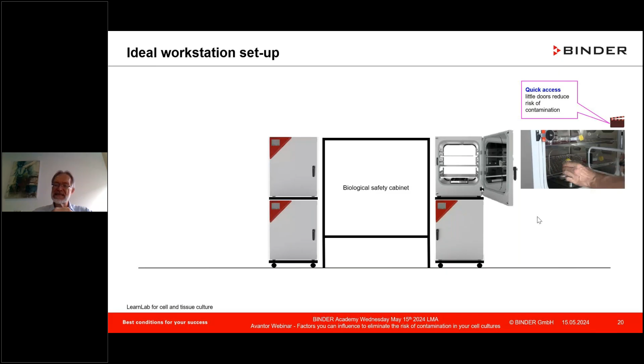Then we have a dual door. This is ergonomic, something which is appreciated when you are actually changing the media. If you're passaging, you can open only in this case - that is not normally the case. The normal case is glass door remains closed and the outer door too. In this case, with a dual door, you have the opportunity to open both doors, outer door and glass door, with immediate access when you're exchanging, when you want to introduce the fresh petri dishes back into the CO2. That's a time-saving little step, not a big deal, but it also improves your contamination management.